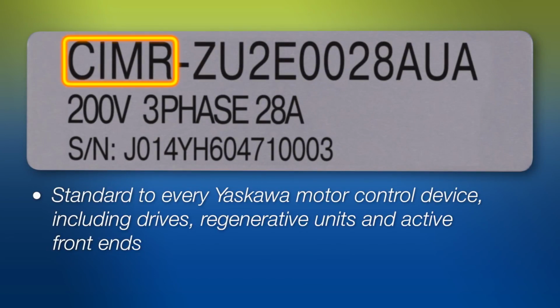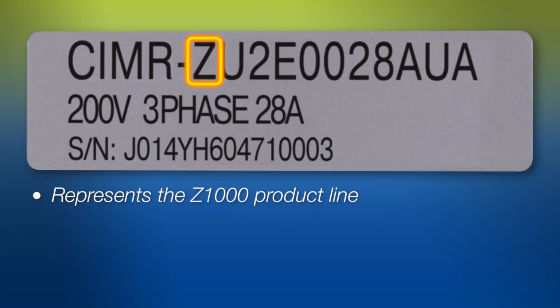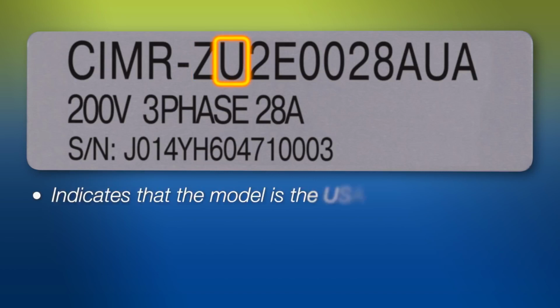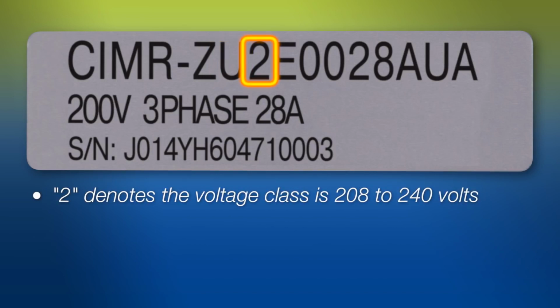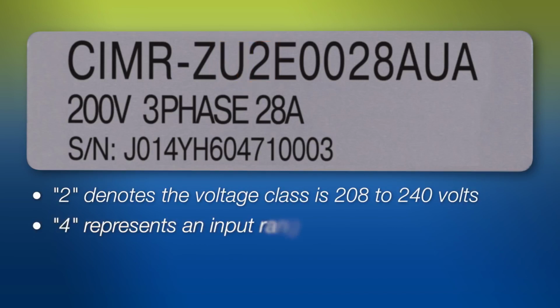CIMR is standard to every Yaskawa motor control device, including drives, regenerative units, and active front ends. The Z represents the Z1000 product line, which is used for commercial HVAC applications. U indicates that the model is the USA specification. 2 denotes the voltage class is 208 to 240 volts. A 4 here would represent an input range of 380 to 480 volts.